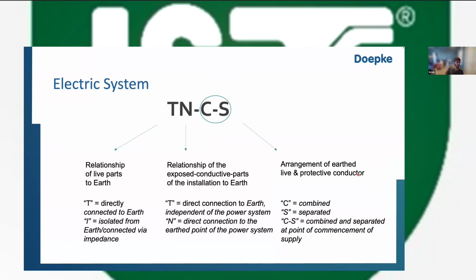Before we get into the actual requirements in the standard, I want to give you a little bit of information about the types of electric systems that we have that are designated by IS 732 and NEC. Each electric system is designated a 2 to 4 alphabet code that explains what kind of system it is. First alphabet designates the relationship of live parts to Earth. Second alphabet designates the relationship of exposed conductive parts, the body of equipment, to Earth. And the third and fourth letters, which are supplemental, not always required, designate the arrangement of Earth, live, and protective conductors. Don't get too bogged down by this. I'm just going to briefly explain what this is and what the implication is for you as someone in vertical transportation.